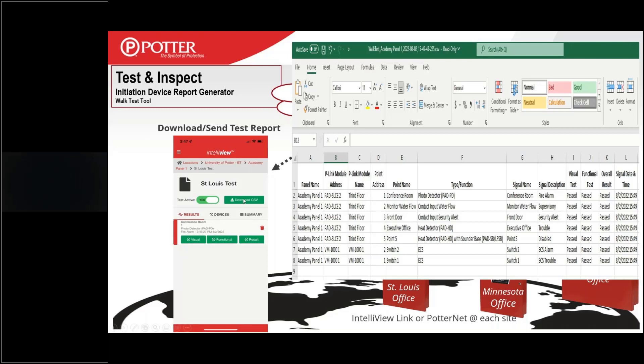You'll see the download CSV file button. Hit that and it'll download a CSV file — if you're on a mobile device, it'll ask where you want to send it, so you can email it or text it. It creates a CSV file you bring into Excel that has all the information for that point: the panel, the SLC, all your labels and addressing. Over to the right is more detail — the signal was in the conference room, it was a fire alarm, and it passed all the visual, functional, and overall checks with date and time. If you had failed any, it would say failed visual.